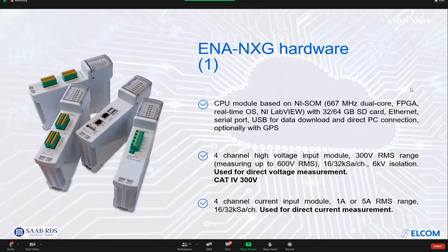So beginning with the hardware inputs, we have a CPU module, which does all the calculation, which has the storage, SD card, GPS optionally input, Ethernet, USB for additional data download. And then we have different input modules. First one, which is mostly used, is the module measuring directly the 3-phase voltage. So it has 4 channels, 300 volts RMS range, measuring up to 600 volts RMS, very high isolation. It's from safety point of view is category 4, 300 volts. So it can be placed in the cabinets which are installed outside.